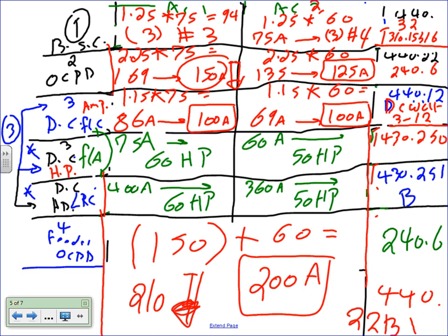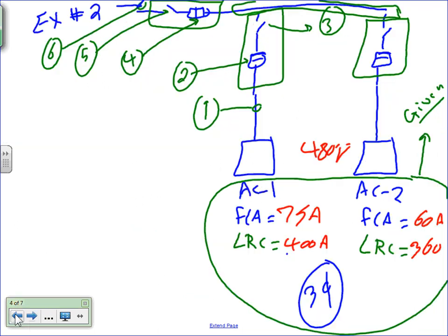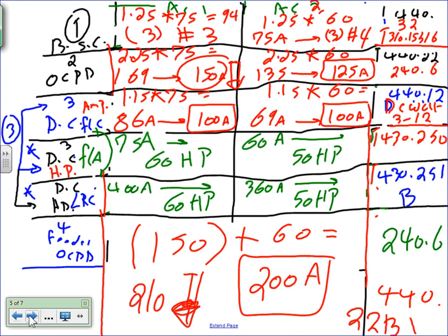Okay? Did they do it wrong? 210, right? And then you go down. You don't go up, you go down. That's the feeder. That's right here. The overcurrent protection device. That's the feeder overcurrent protection device, right here, number 4. And that's in 440.22, I think. 440.22(B)(1).